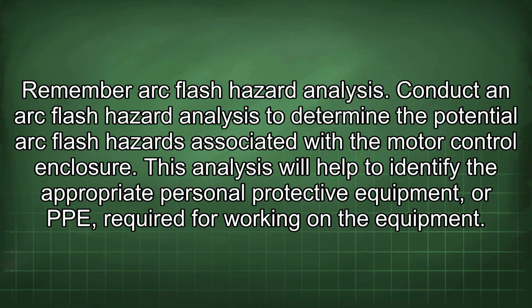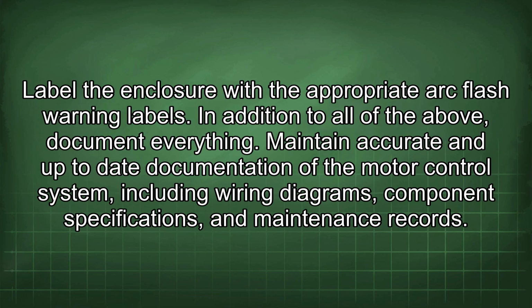Remember arc flash hazard analysis. Conduct an arc flash hazard analysis to determine the potential arc flash hazards associated with the motor control enclosure. This analysis will help to identify the appropriate personal protective equipment, or PPE, required for working on the equipment. Label the enclosure with the appropriate arc flash warning labels.